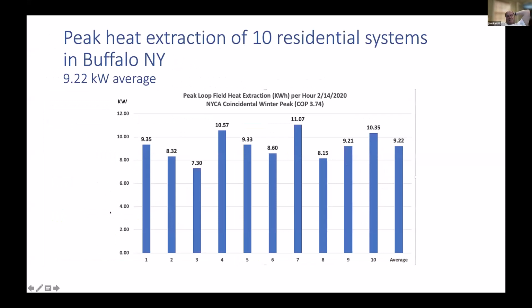Now, these are the 10 single-family homes in the Buffalo area. We looked it up at the coincidental peak in 2020, and they were operating at an average COP of 3.74, pulling an average of 9.22 kW out of the loop field as thermal energy during that peak hour. I raised the question, how much is that worth?